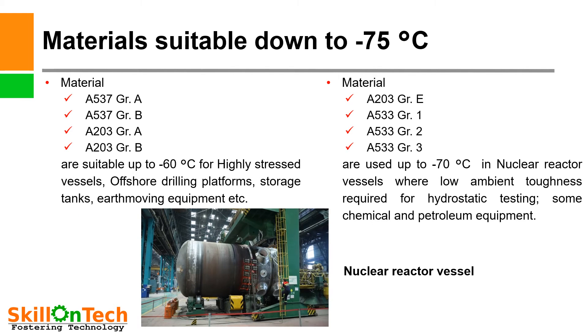Materials suitable down to –75°C. For example, materials such as A537 grade A, A537 grade B, A203 grade A, and A203 grade B are suitable up to –60°C for highly stressed vessels, offshore drilling platforms, storage tanks, earth moving equipment, etc.